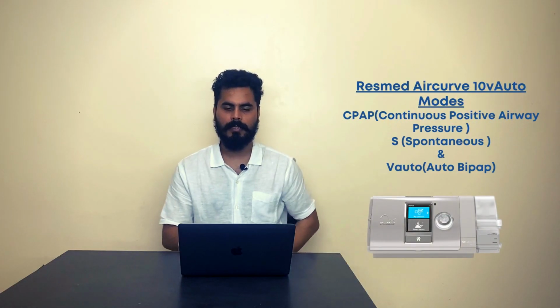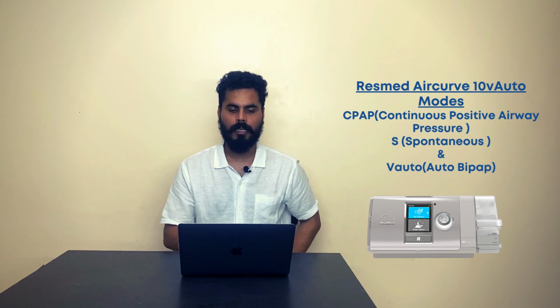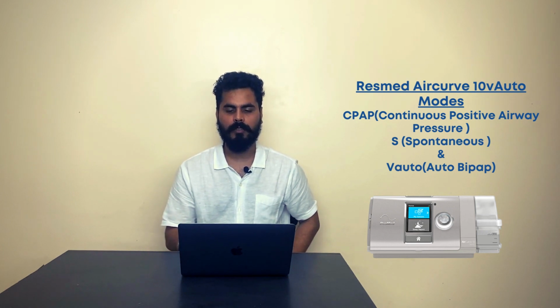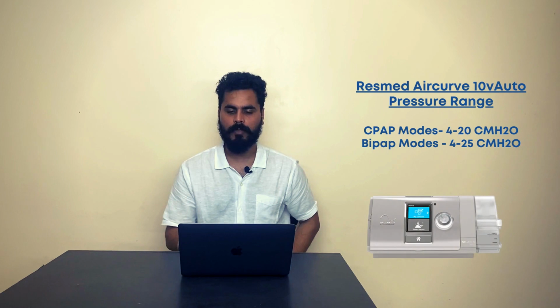Now let's discuss the clinical features of this model. There are three major modes available in this device: one is CPAP, one is S, and one is VAuto. Now if we talk about the pressure range of this machine, in BiPAP modes the pressure is 4 to 25 centimeters of water and in CPAP mode it is 4 to 20 centimeters of water.